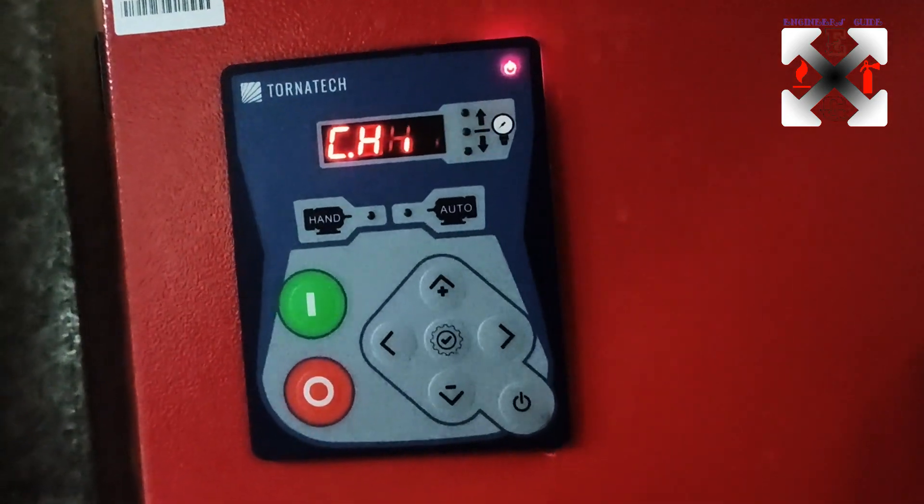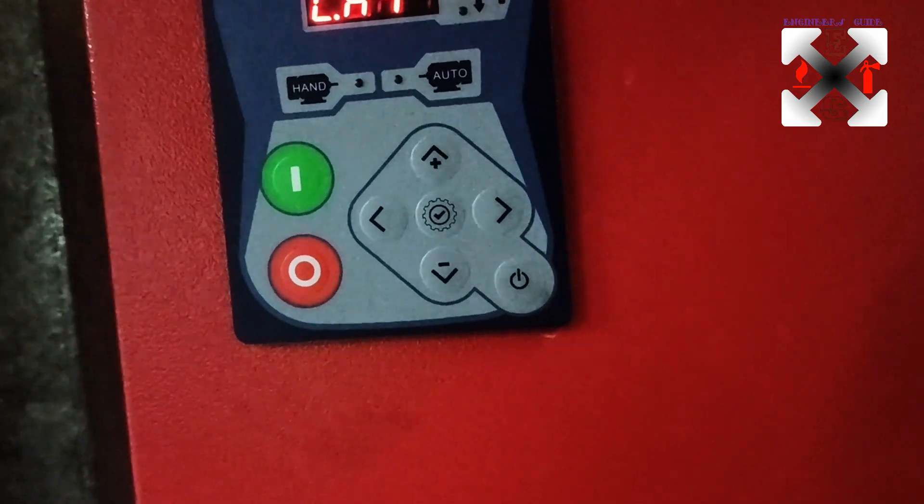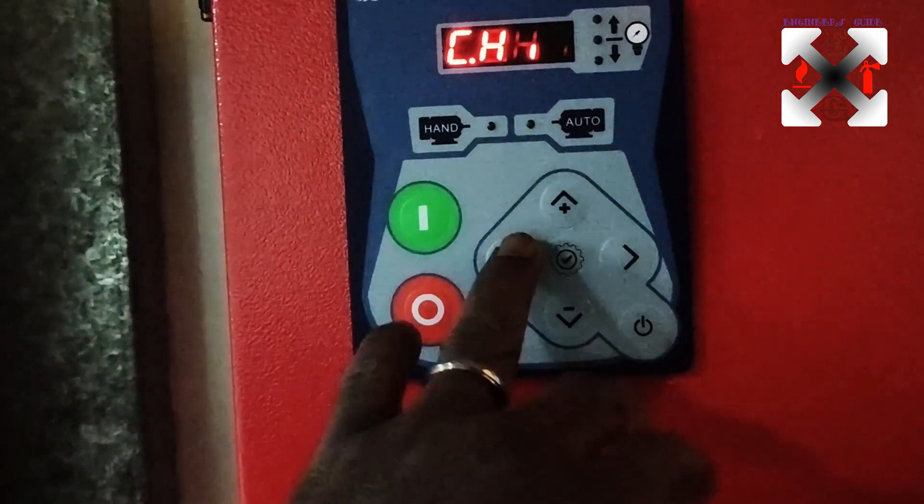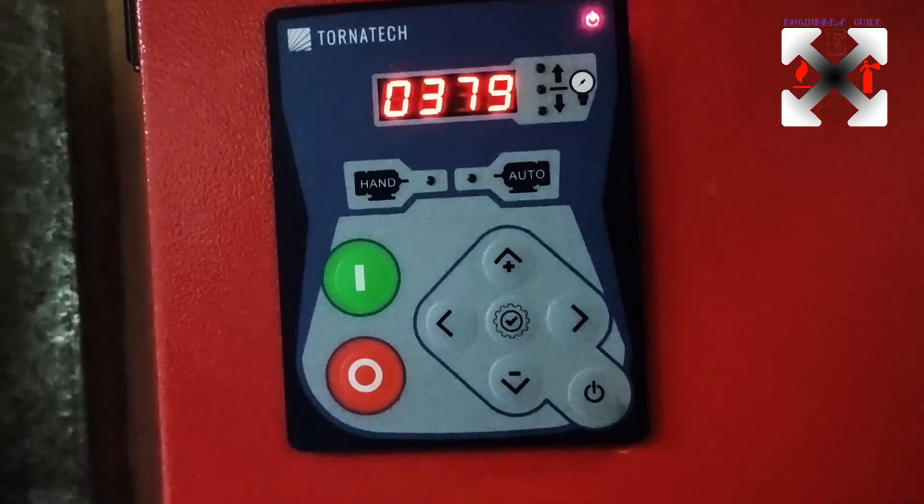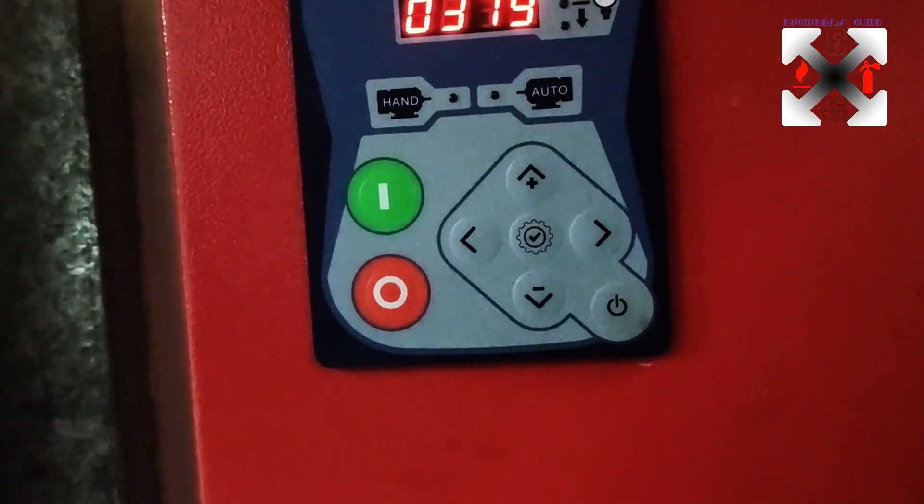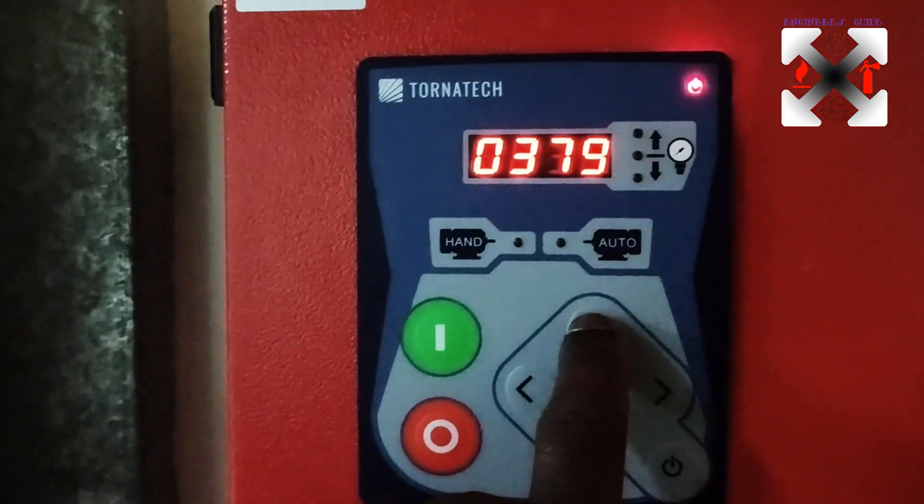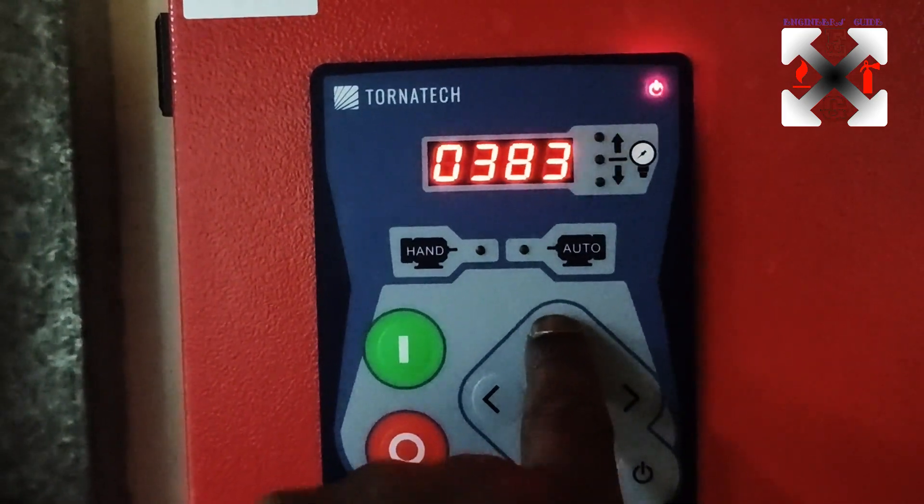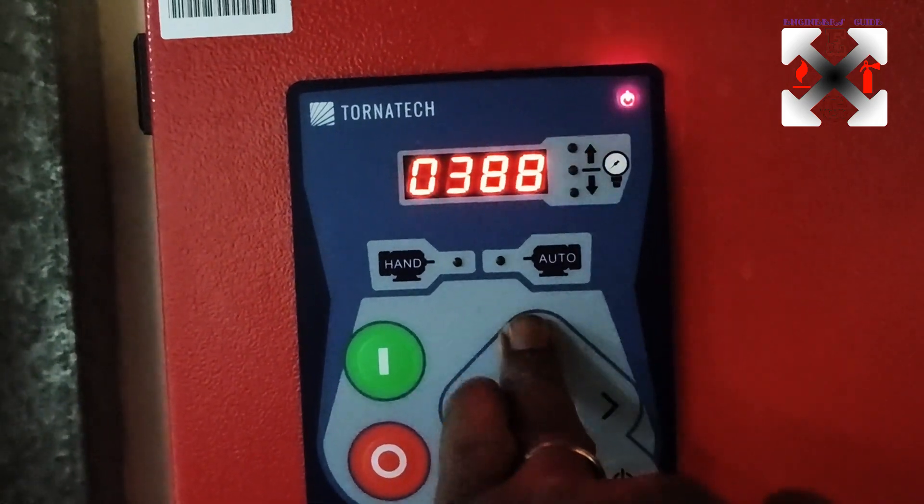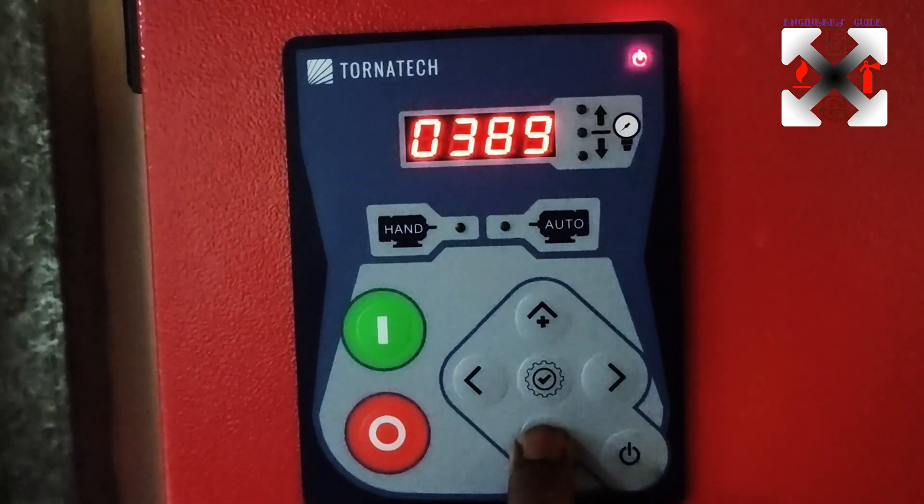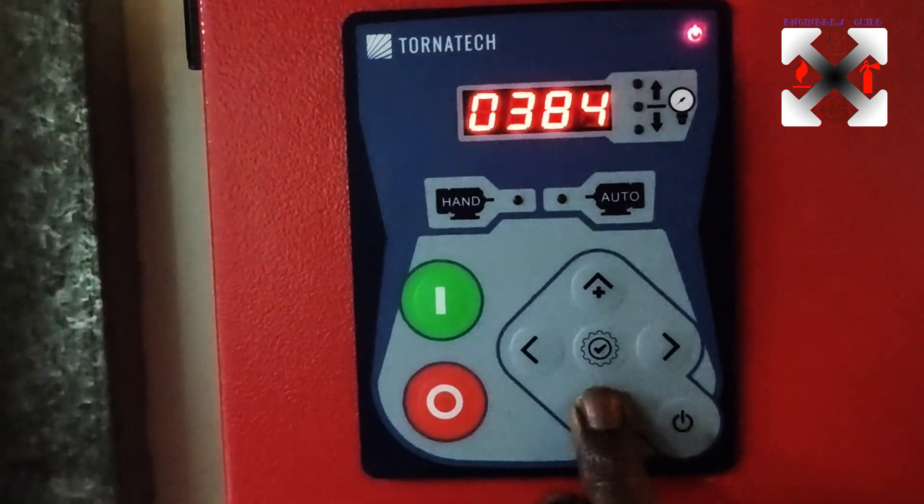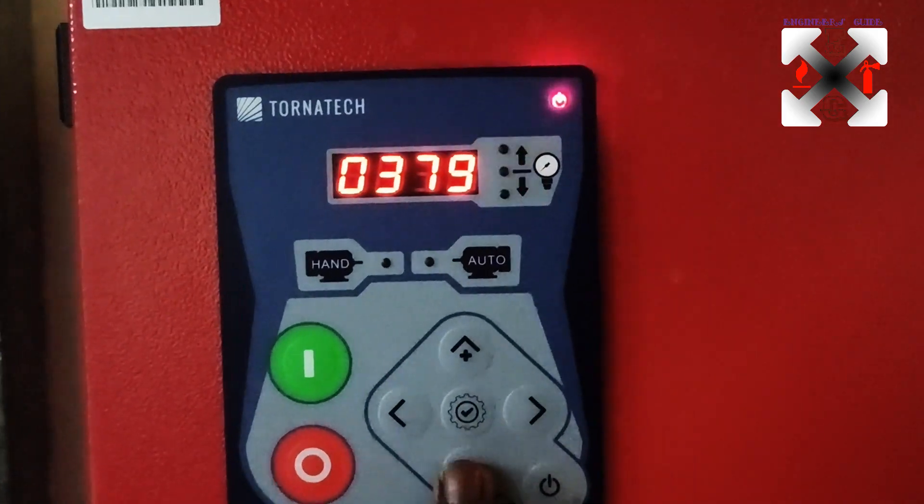Then you see the maximum pressure of the controller where it stops, then you calibrate it against that. So for here if I pressurize, let's say I'm getting 380 or 390. So if it's 390, I would just put 390. But this has been calibrated already, so I will just leave it at 379.